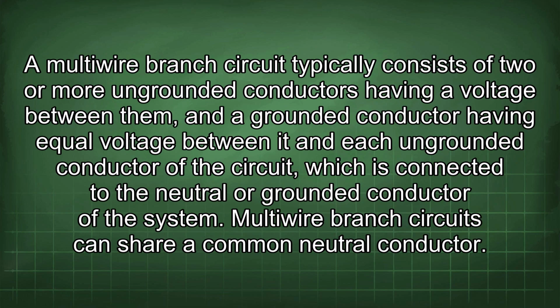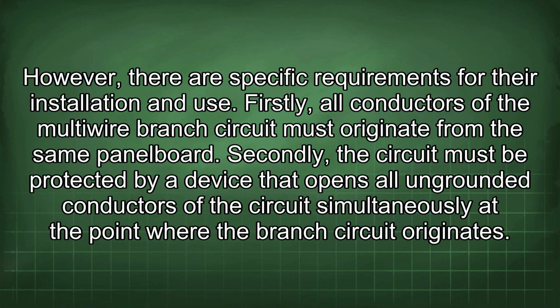A multiwire branch circuit typically consists of two or more ungrounded conductors having a voltage between them, and a grounded conductor having equal voltage between it and each ungrounded conductor of the circuit, which is connected to the neutral or grounded conductor of the system. Multiwire branch circuits can share a common neutral conductor. However, there are specific requirements for their installation and use.